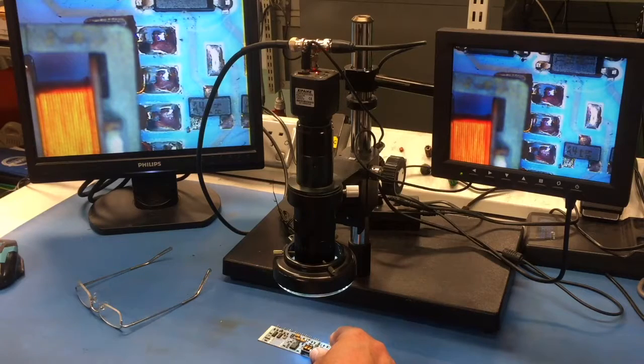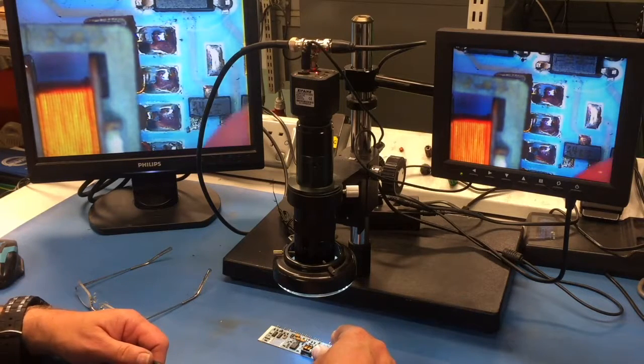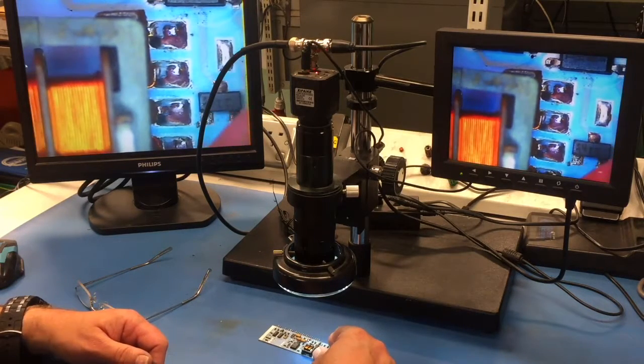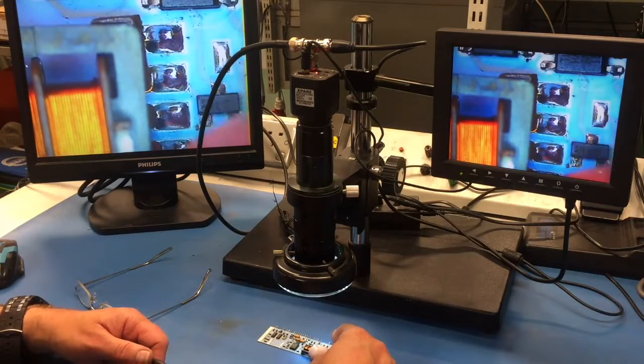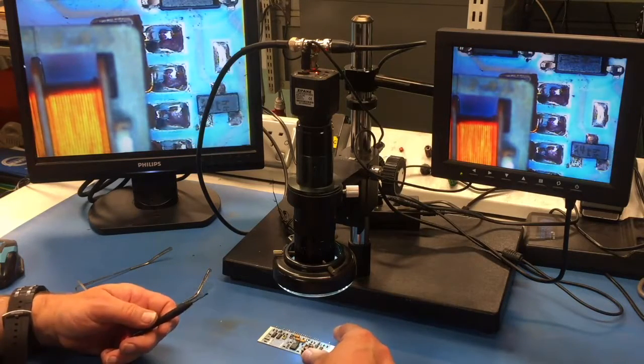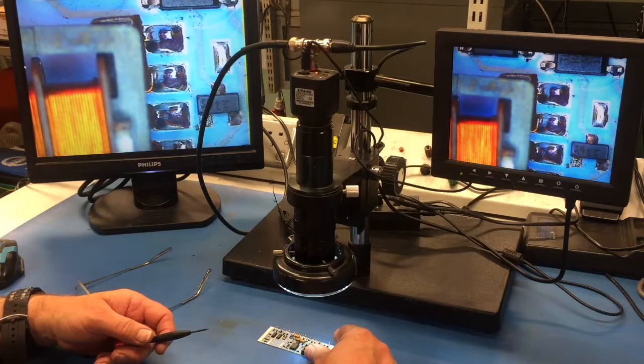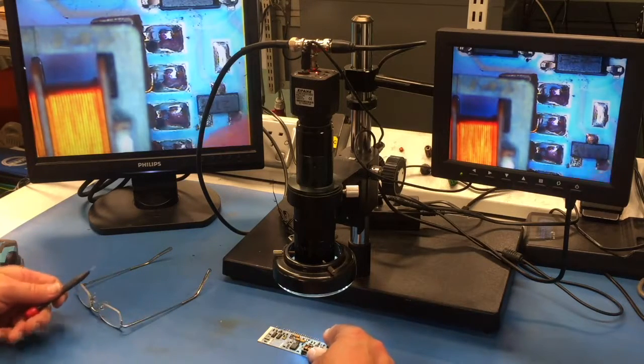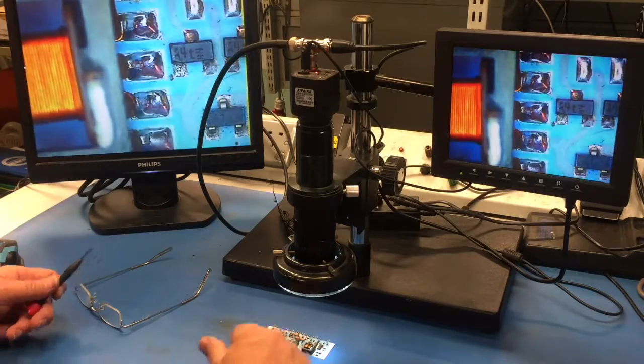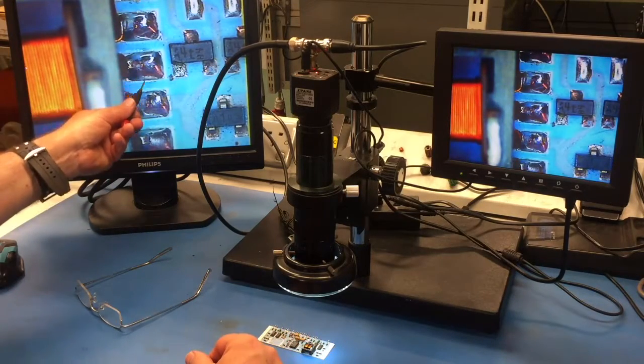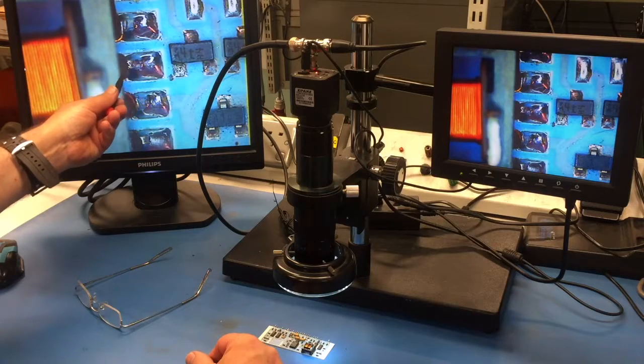Hi again, Jeff. I see we're at our microscope inspection bench looking at the hybrid tile that you've just replaced the transformer on. Can you tell me what you're looking for now, please? Yes, the flux has been cleaned off the solder joints, and we're checking that the solder joints are good. There are no shorts or breaks. So we're just looking at the joints, and what we're looking for is a nice profile of the solder on the lead out leg.